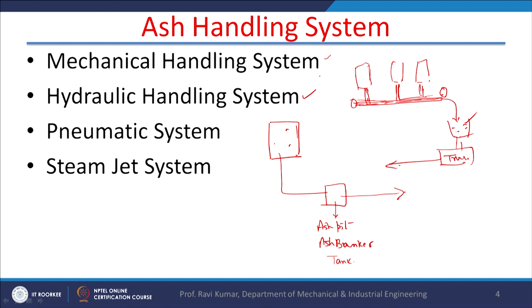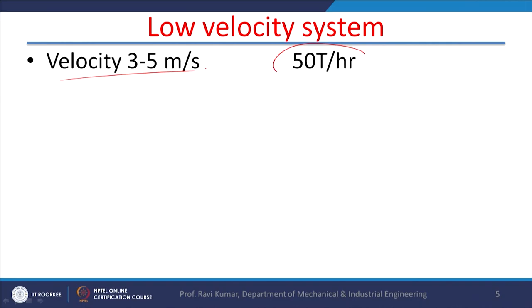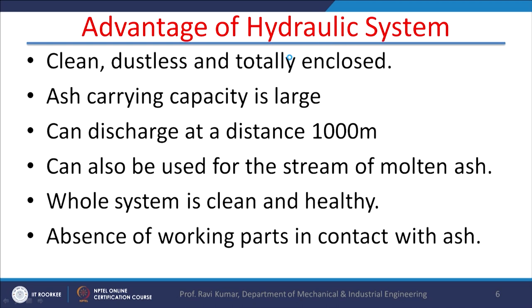There are pneumatic systems also, where ash is removed under pressurized air. There are steam jet systems where steam is injected on the ash, making a slurry which is then removed from the thermal power plant. These are all low velocity systems, and the mechanical type can remove up to 50 tons of ash per hour — that is a limitation of the mechanical ash handling system.